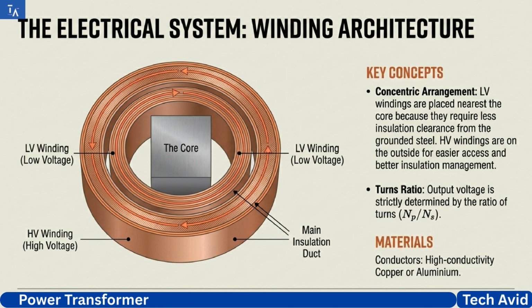Wrapped around the core are the windings, precise coils of copper or aluminum. They have a strict architecture. Low voltage windings sit closest to the grounded core as they need less insulation. High voltage windings are on the outside, where there's more space for the thick insulation they require. The rule is simple. The ratio of turns between primary and secondary coils dictates the output voltage.